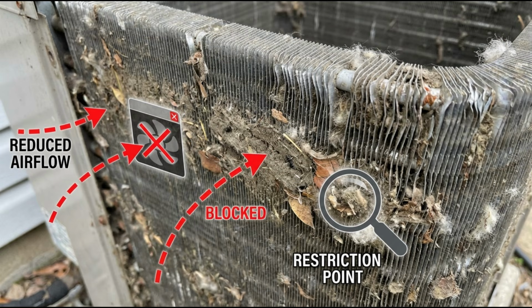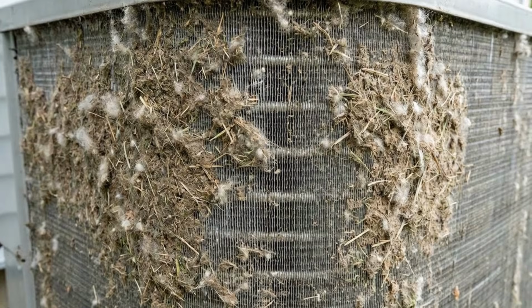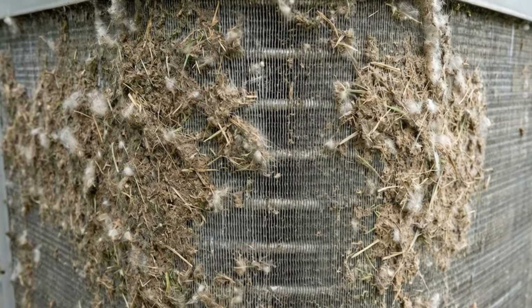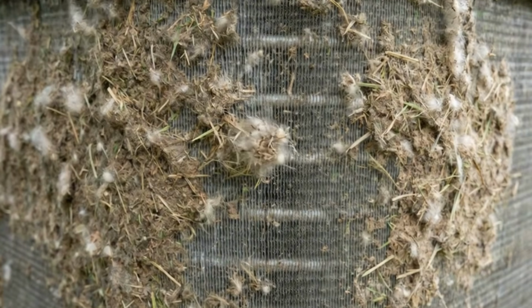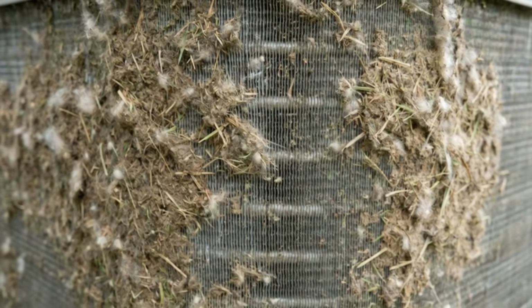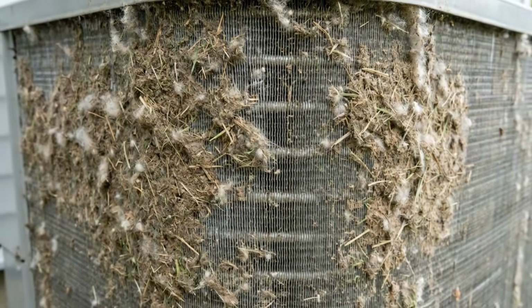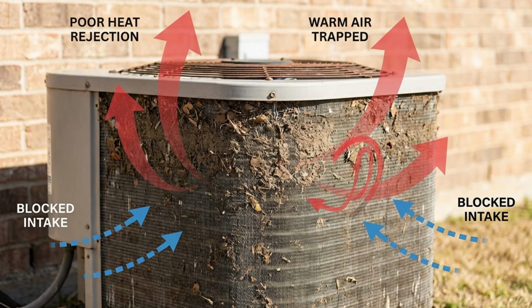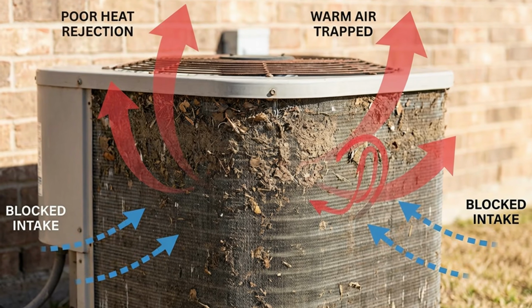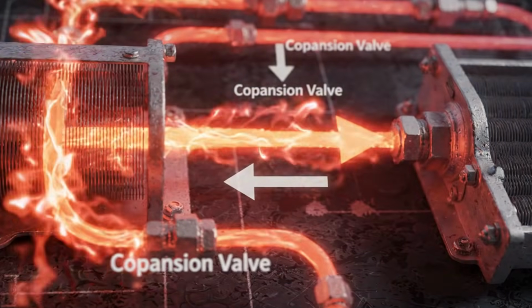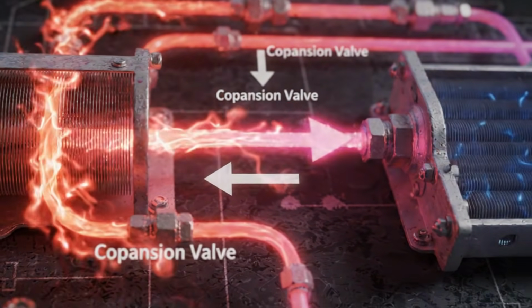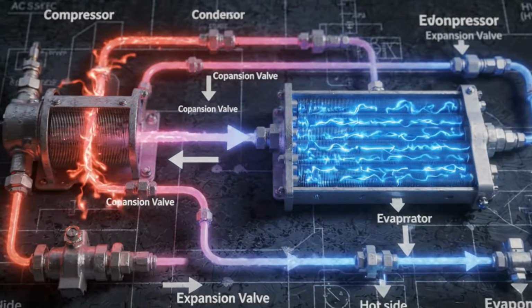What kills outdoor units prematurely is coil restriction. The aluminum fins on the outside of your condenser get clogged with cottonwood seeds, grass clippings, pet hair, and general debris. When those fins are caked, your system can't reject heat efficiently. The refrigerant runs hotter, the compressor runs hotter, head pressure climbs, and compressors that run hot consistently just don't last as long as ones that don't.